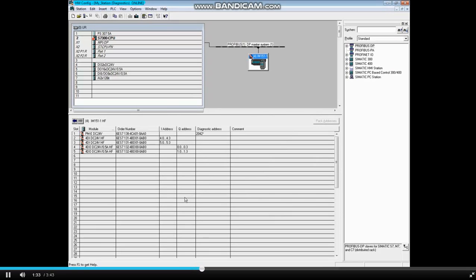We will now do a physical inspection of the system to see if we can determine what's wrong. It could be a Profibus cable, a connector, a failed interface module, no power to the interface module, or something else. After inspection, it was determined that the wires in the Profibus connector to the ET200S station were not making a solid connection. The cable was trimmed, the wire newly stripped with a Profibus cable strip tool, and a new connector put on the cable.